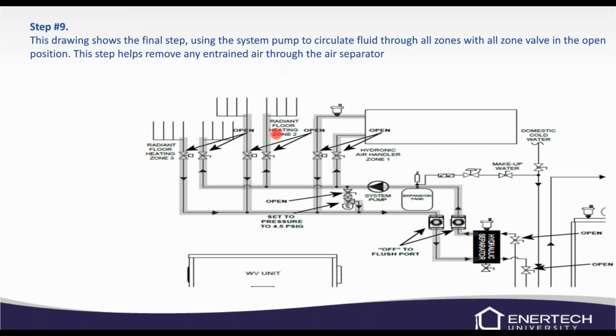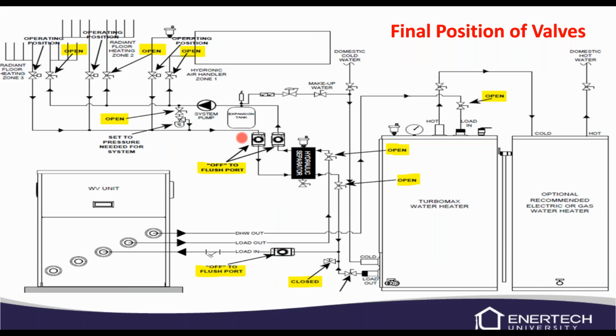After all the zones are flushed, we want to open up all the valves and flush through the whole circuit in case there are any micro bubbles still left in it. This is the final position of all the valves. So after you've flushed, make sure all your valves are in the correct position, and we're ready to go because we're going to start up the equipment after we get all your valves open. This is a nice little highlighted area to let you know which valves are open throughout the circuit.